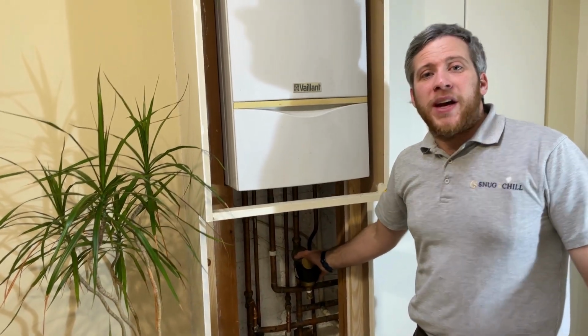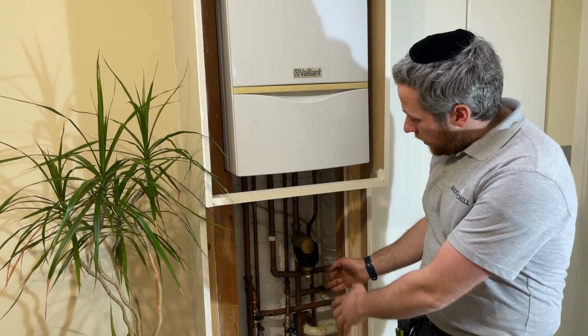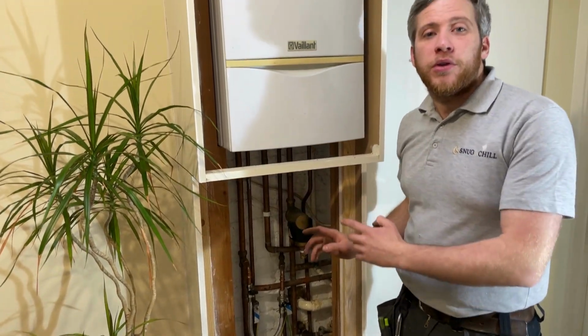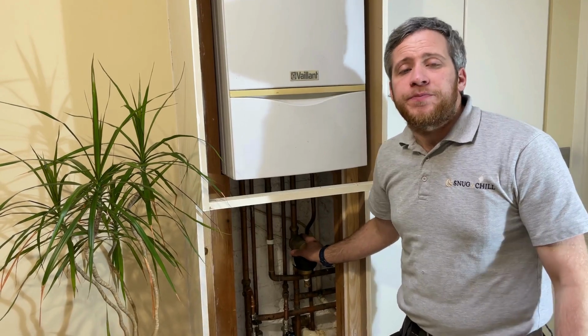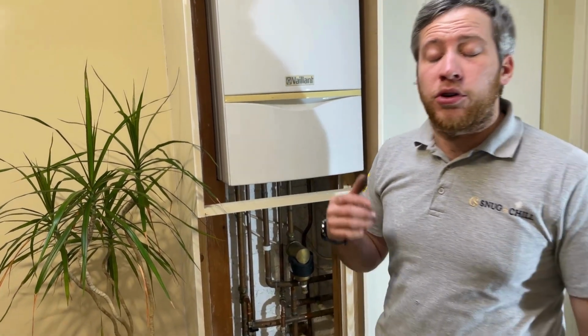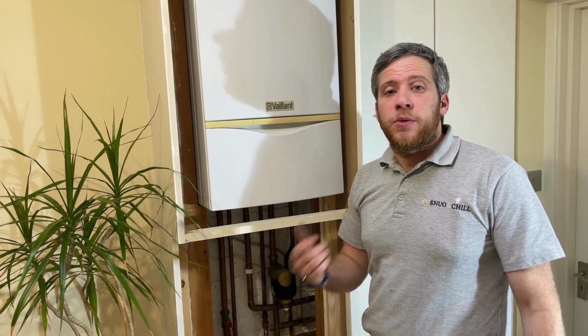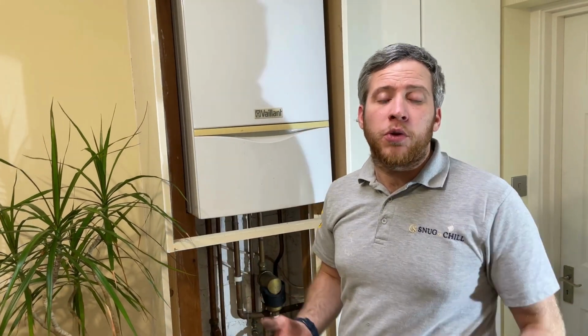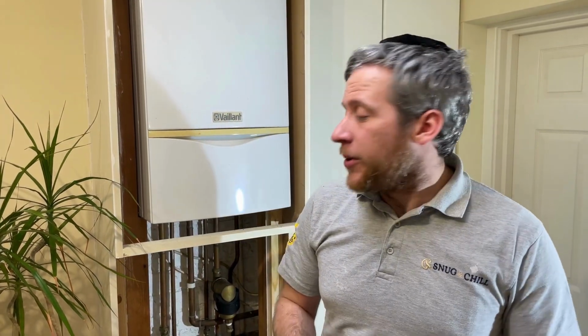So for example, this magnet filter prevents the water from going back with dirt to the boiler and it catches it in the filter. It prolongs the life of the boiler, and of very sensitive parts in the boiler which eventually do break if the dirt was to go into the boiler. For example, the plate heat exchanger is a very fragile part in the boiler. With any dirt catching in it, that plate heat exchanger is blocked. Other sensors and little pipe work where the boiler flows water through, if that gets blocked, sometimes it can even mean a new heat exchanger, which can be very costly.